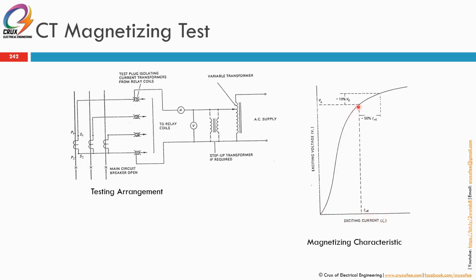There will be a point which we call the knee point. Knee point is a change of 10% in excitation voltage which causes a 50% change in excitation current. So that is the starting of that knee point. The stable and operating region of the CT would be below this knee point. Anything above this knee point is considered to say that the CT may be saturated. Alright. So anything below the knee point, the CT should be working and functioning well within the tolerance and error of its CT rating. Alright.